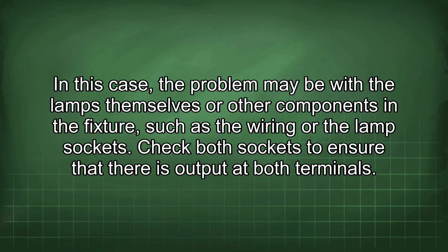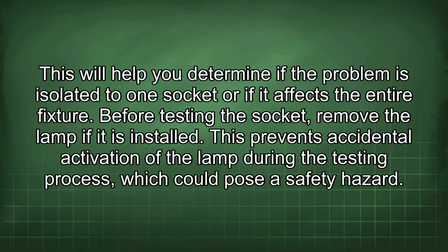Check both sockets to ensure that there is output at both terminals. This will help you determine if the problem is isolated to one socket or if it affects the entire fixture. Before testing the socket, remove the lamp if it is installed. This prevents accidental activation of the lamp during the testing process, which could pose a safety hazard.